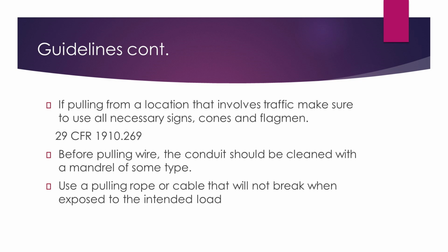One thing I will say is if you have long runs of wire and you're pulling this stuff through there, with little rocks and stuff like that, it's going to end up nicking the insulation of that wire over and over again, damaging it. Hence, now you have spots where you could possibly have some kind of fault.